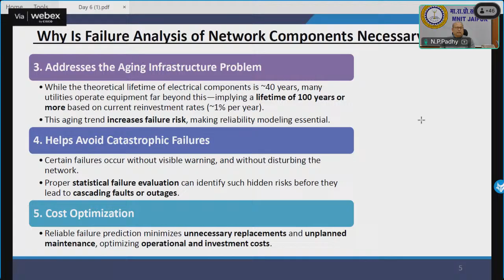We need to collect and evaluate real world historical failure data from the distribution network and categorize failure causes and locations -- data on every device across the world: what is the failure rate of cables, relays, switch gears, transformers, poles, generators, and so on. Once you get that data and their locations, this analysis is essential to build accurate reliability models for various components in the distribution system. For example, if 100 generators worldwide failed before their expected lifetime, that needs to be investigated -- was it mechanical failure, insulation failure, or electrical failure? Once you analyze this, you know what maintenance strategy needs to be adopted by the utility for that device, and that is the future.